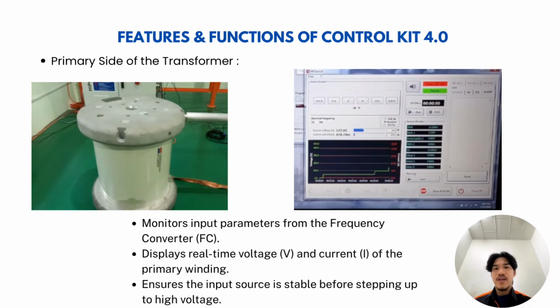For the next slide, the primary side of the transformer. The function is monitoring the input primary parameters from the frequency converter and displaying the real-time voltage and current of the primary winding. It ensures the input source is stable before stepping up to the high voltage.